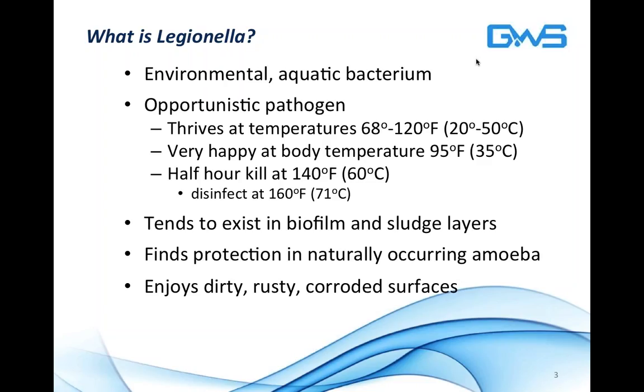And if you want to disinfect, you have to get your water temperature up to about 170 degrees or have a half-hour kill rate at about 140 degrees Fahrenheit. Legionella will hide in biofilm, sludge layers, and dirt, and it finds protection in naturally occurring amoeba and protozoa in the environment. It also enjoys dirty, rusty, corroded surfaces, which is why cooling waters, especially, are a place that Legionella can harbor and survive quite well.